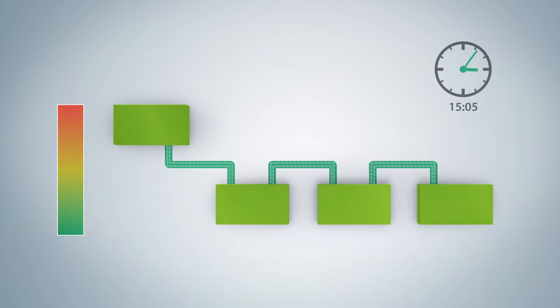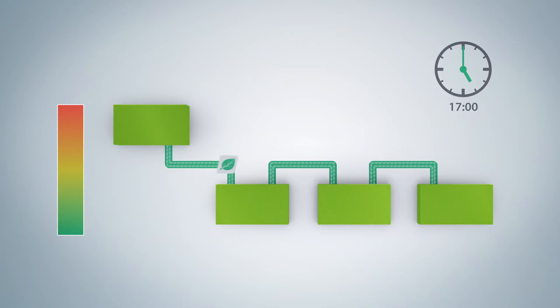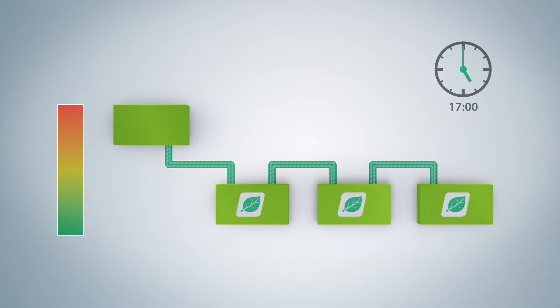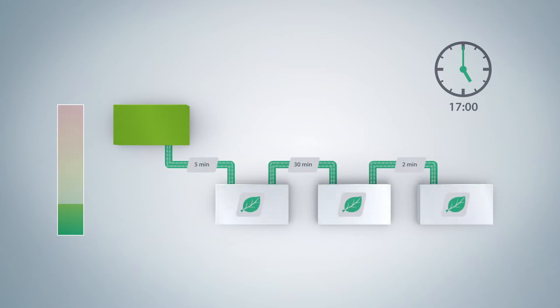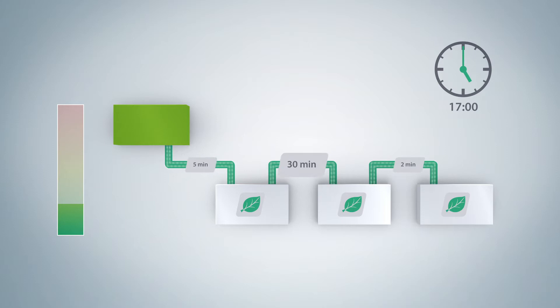Standardized ProfiEnergy commands can be used to switch unneeded devices to energy saving mode. Typical examples of pauses are production-free nights and weekends. Devices signal information back to the controller on the length of their switch-on phase.